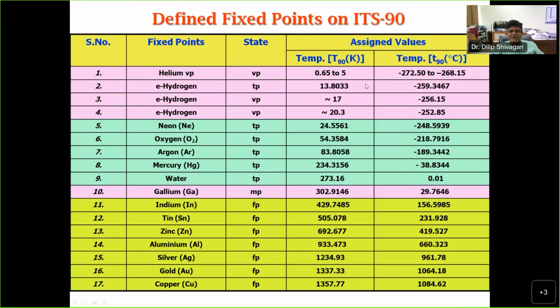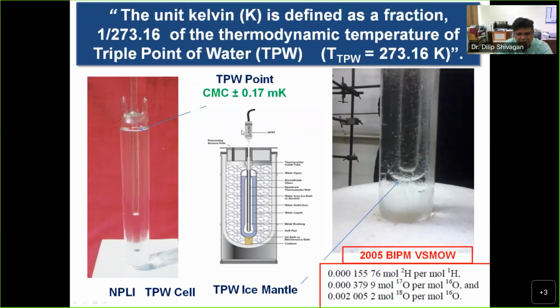So these are the levels of uncertainties at different temperatures, because as I said, we need to go to that temperature and realize it. Therefore, over the intermediate temperature range, we have 17 fixed points defined for the establishment of the scale. So again, the TPW was very important. Critically, we have evaluated the measurement uncertainty. For this, you have to revisit sometimes how this state is being created. It's a really crucial experiment, and in a new way, because whenever we have to carry out a periodic or intermediate test, you need to have a very fixed source. Either an ice point or something you need to have in your laboratory.